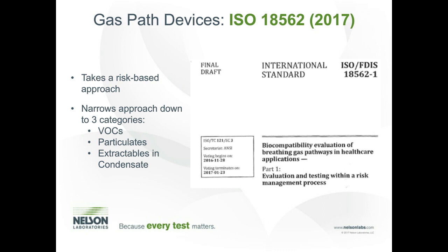The beauty is that it takes a risk-based approach to gas path devices, and it narrows down the potential risk from these devices to three categories. There's volatiles that the device could release that the user could be exposed to, or there could be particulates released by the device that could be a concern. And finally, if it's a gas path device that has the potential to form condensate on the inside of the device, this liquid could be contacting the materials, and then that could be transferred directly to the patient in its liquid form.